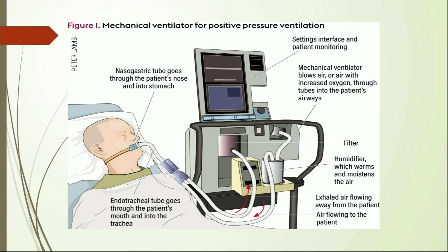Now we are going to see the components of a ventilator. A ventilator can probably be easily understood if it is pictured as a black box. It is plugged into an electrical outlet or high pressure gas source, and gas comes out the other side. The person who operates the ventilator sets certain knobs or dials on a control panel, that is the user interface, to establish the pressure and pattern of gas flow delivered by the machine. Inside the black box, a control system interprets the operator's settings and produces and regulates the desired output.